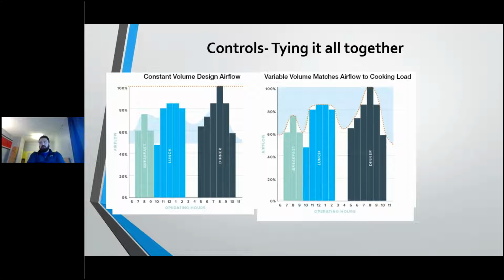The final component that we're going to speak on, as far as the kitchen ventilation system is concerned, is your controls. There are two types of controls in the market. First and foremost, controls are required per IMC to be an interlock to the exhaust fans and the makeup air fans. The way that interlock is achieved is that the exhaust hood is going to come with a temp probe, either in the exhaust hood cavity or in the exhaust hood ductwork. And that temp probe is going to be sensing the temperature underneath that exhaust hood.